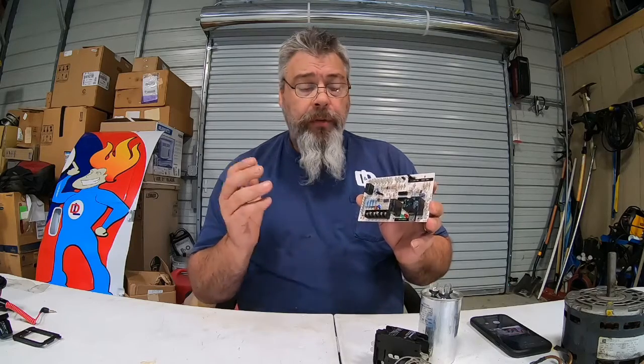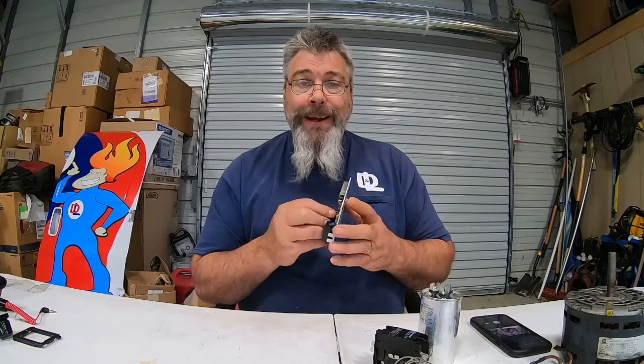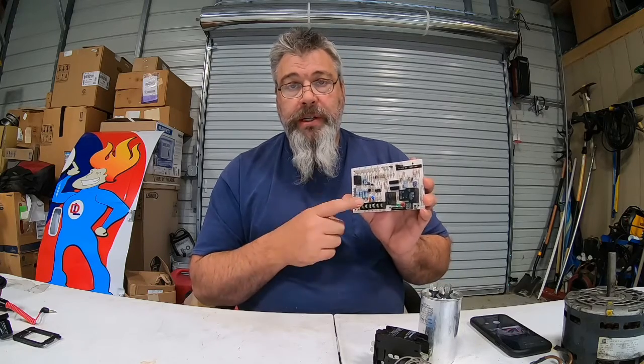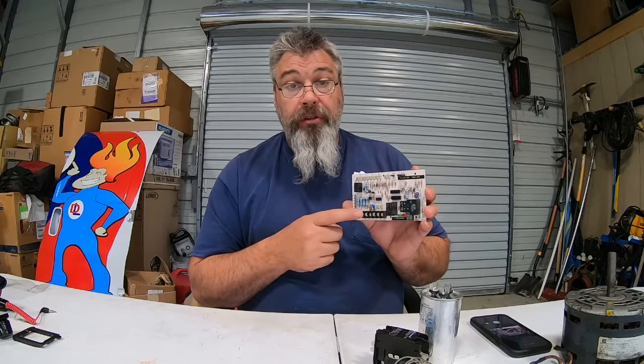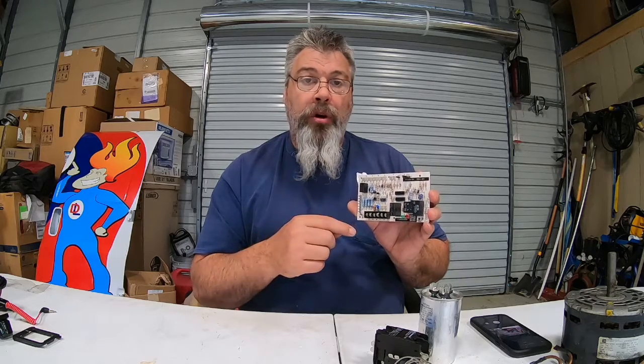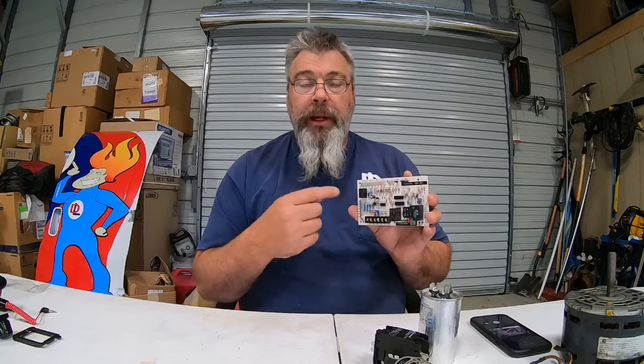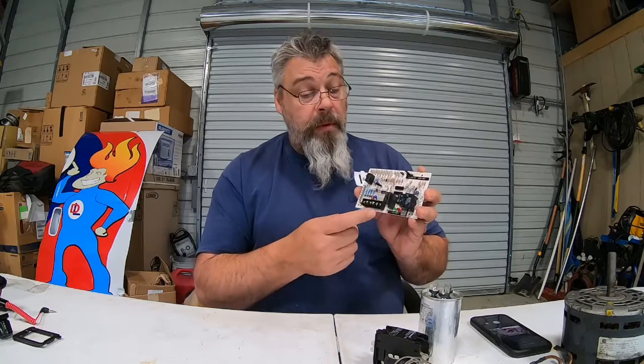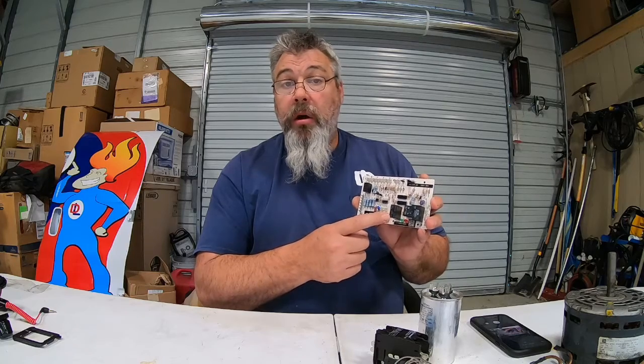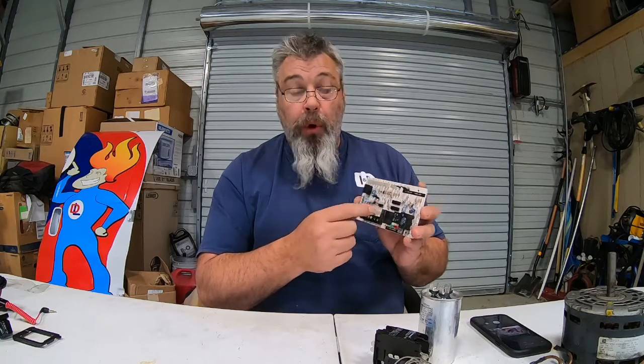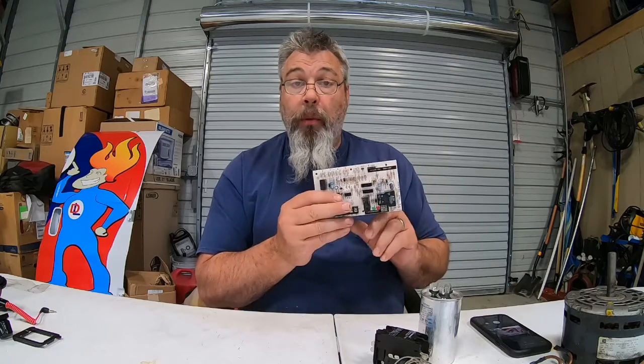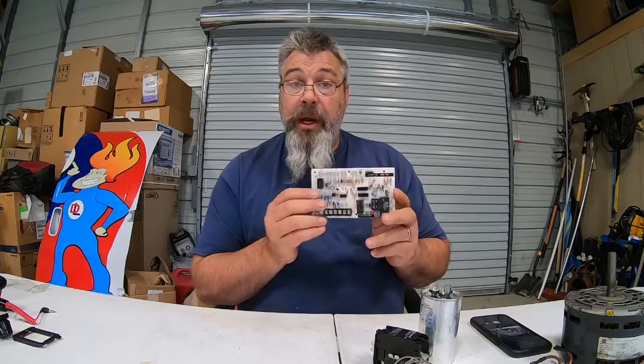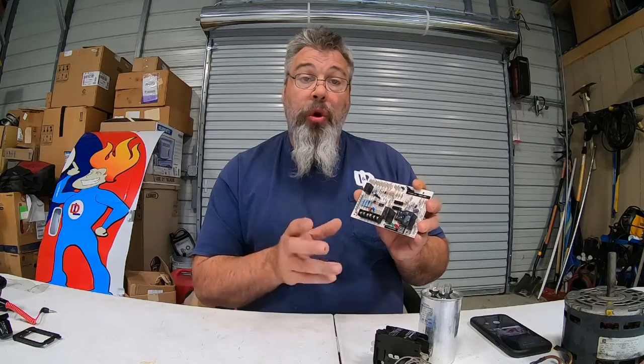These will fail in the midst of summertime during a storm. They're circuit boards. They're very temperamental to electricity. When I say temperamental, it doesn't take much to burn one of these up. Rarely do we see it, unless what happens is in the wintertime when it goes into defrost, we'll find that it's not going into defrost properly, and that's because it probably got a power surge through the summertime that either damaged the defrost relay or damaged the internal components of the board where it doesn't allow voltage to go through. So a control board is another one that's in your heat pump. And in some AC units, it's rare, but most of the time it's in your heat pump. This also controls defrost.